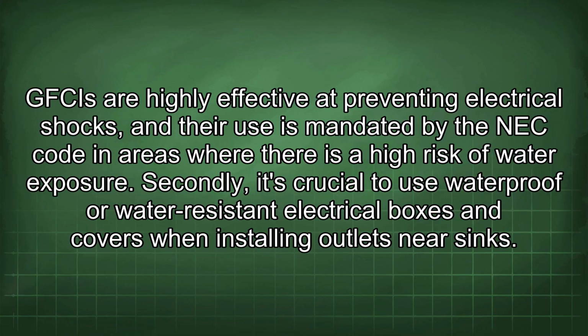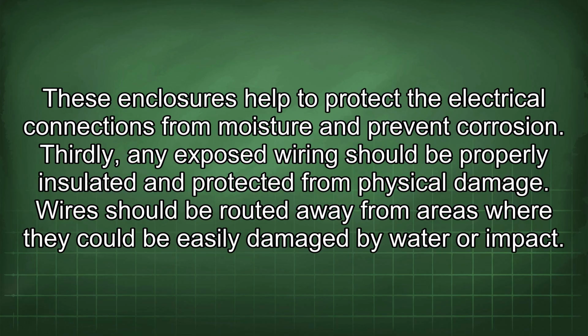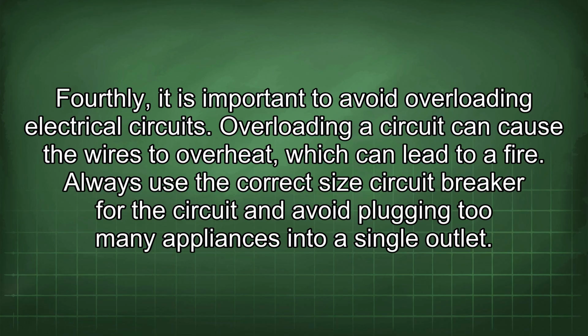Secondly, it's crucial to use waterproof or water-resistant electrical boxes and covers when installing outlets near sinks. These enclosures help to protect the electrical connections from moisture and prevent corrosion. Thirdly, any exposed wiring should be properly insulated and protected from physical damage. Wires should be routed away from areas where they could be easily damaged by water or impact. Fourthly, it is important to avoid overloading electrical circuits. Overloading a circuit can cause the wires to overheat, which can lead to a fire. Always use the correct size circuit breaker for the circuit and avoid plugging too many appliances into a single outlet.